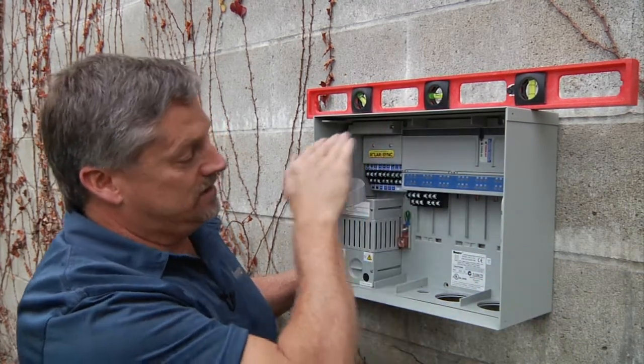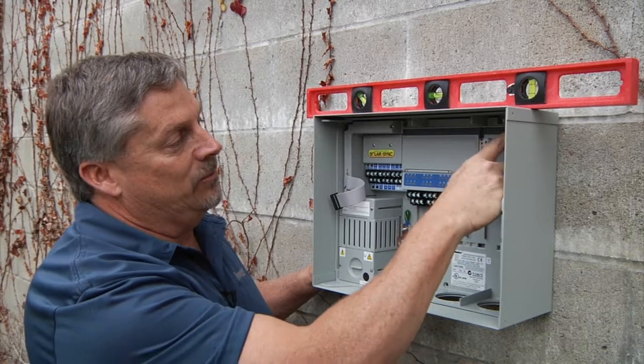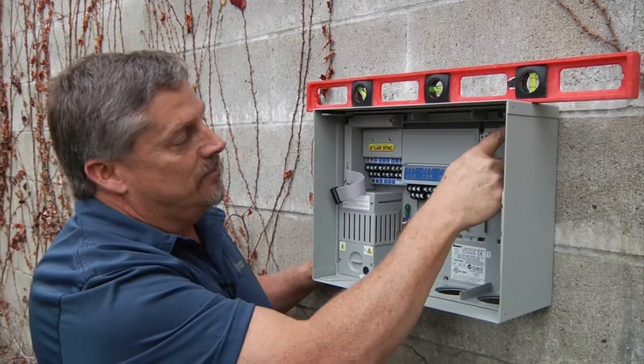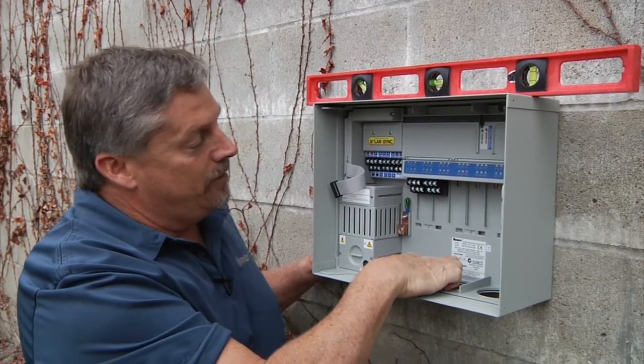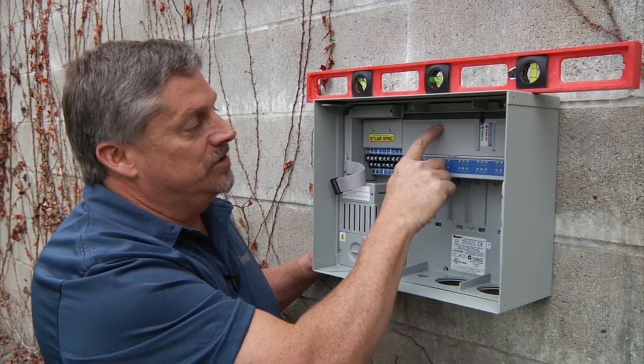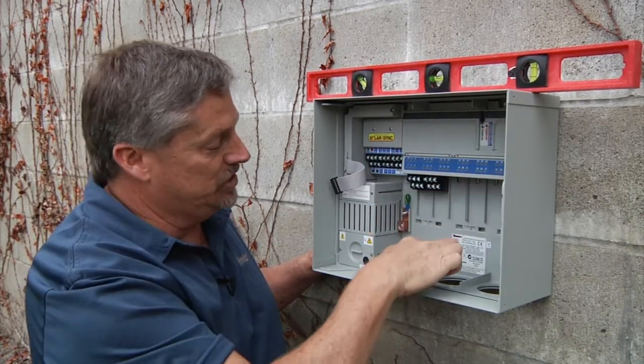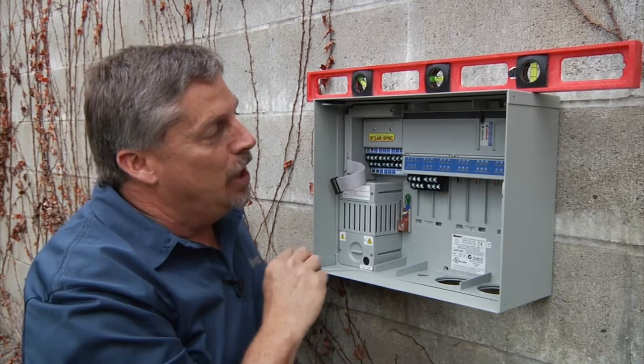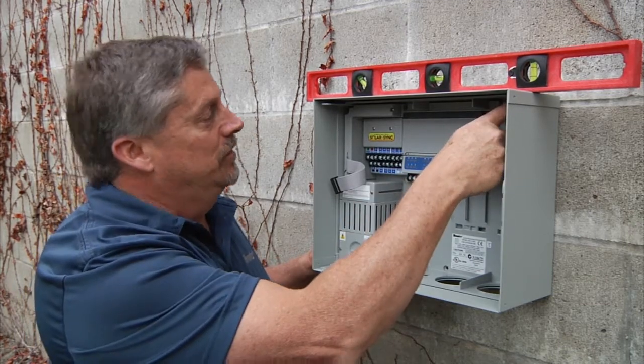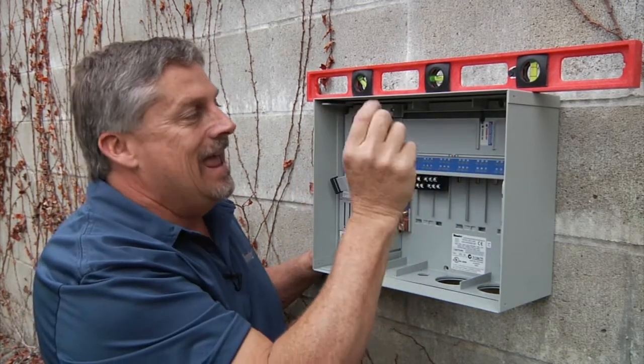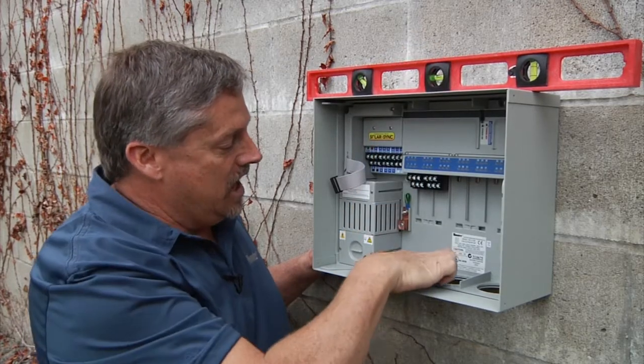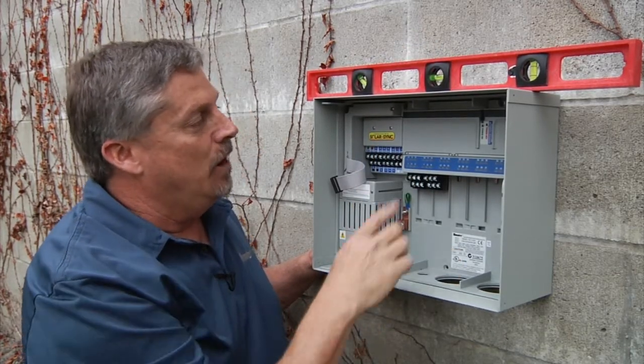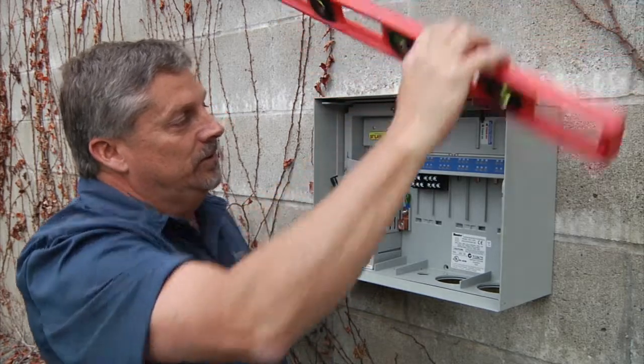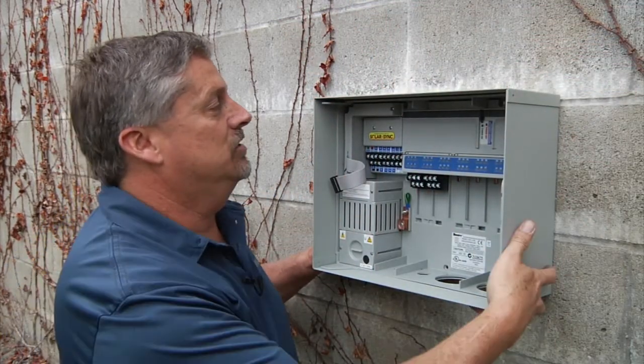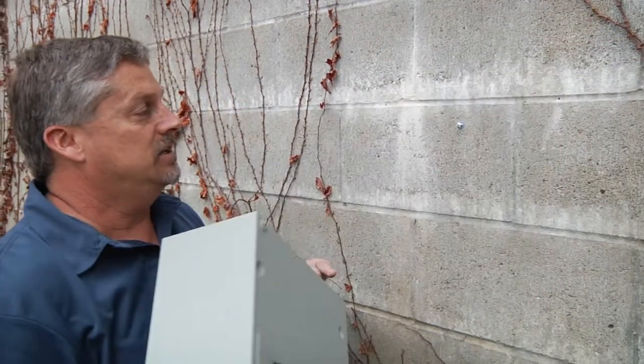And once I have the box all nice and level, I've got 3 more locations: top left, top right, and bottom center. Now remember, we're hanging the box right now on that top center screw. That's going to stay in place, but we want these 3 additional holes for additional support. Use whatever tools you have available to reach through the top left and top right and score the mounting surface, as well as here in the bottom center. Once those 3 spots are marked, we can take the level off and the controller off the wall and go ahead and install anchors and screws in those 3 locations.